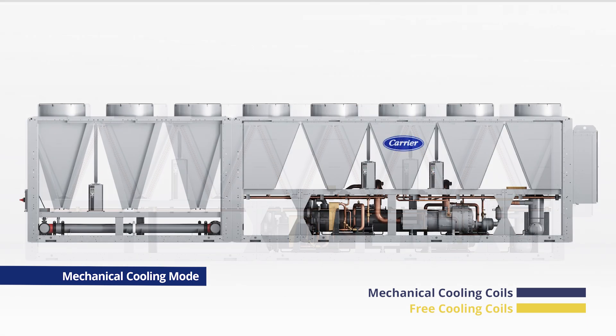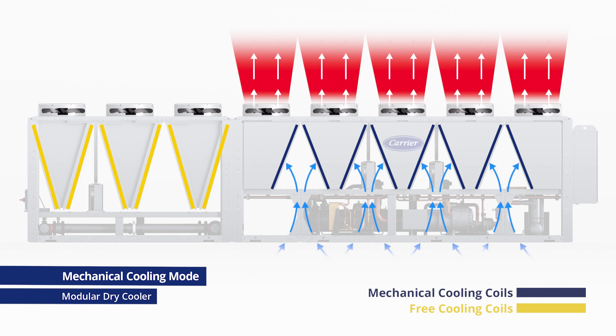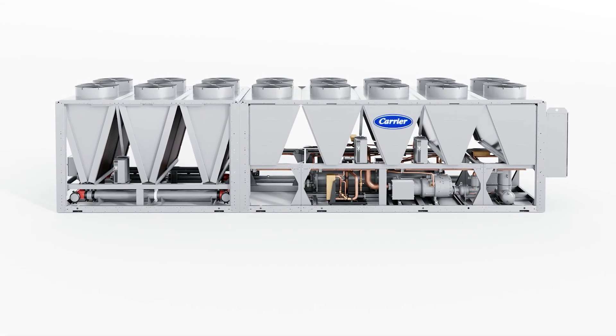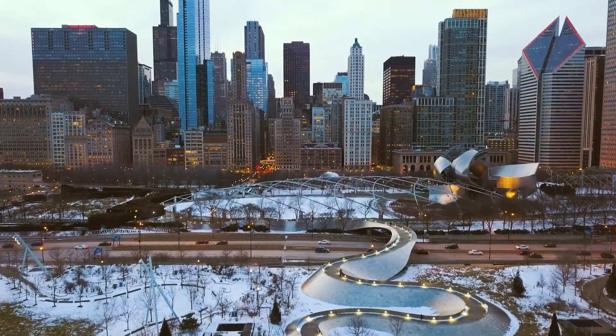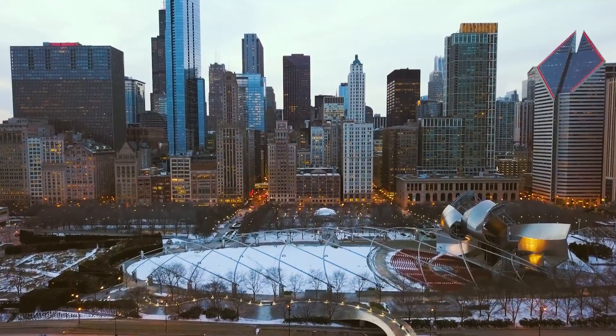The modular design is different. When it's in mechanical cooling mode, the air flows only over the mechanical cooling coils that are in use, while the fans for free cooling are turned off, saving energy. When the ambient temperature is low enough, mechanical cooling can shut off completely, and the set point can be met by free cooling mode alone.